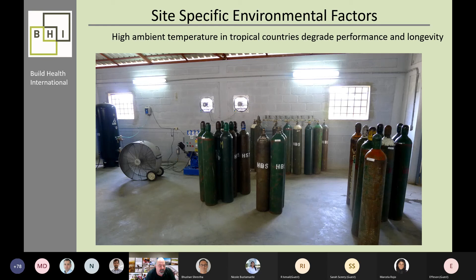Ambient temperature, especially in tropical countries, is again, a high ambient temperature is something that's really not paid enough attention to. Especially in tropical countries at low elevations, you have extreme temperatures, and heat really degrades the performance and the longevity of these big motors and compressors. This is an example of an installation in Haiti where there wasn't adequate ventilation. The two wall fans were added. Those didn't do it. The floor fan was added. That didn't help. This is a plant that is constantly breaking down because of the heat. Next slide.